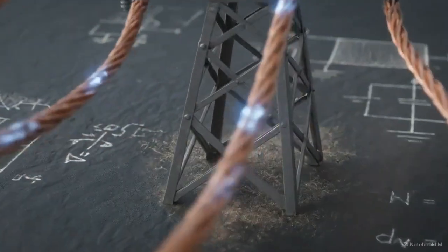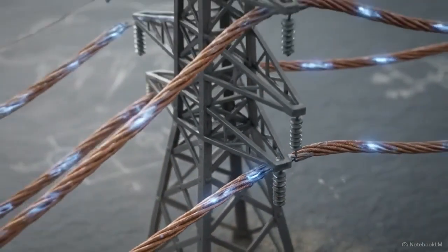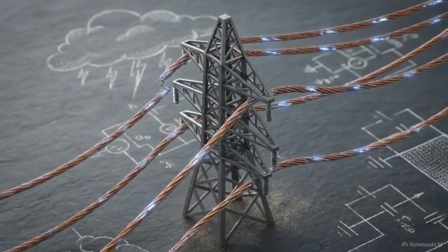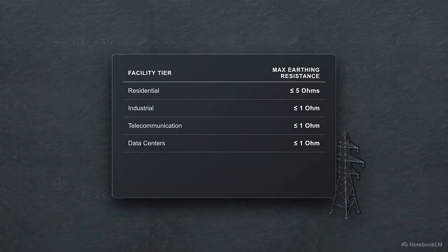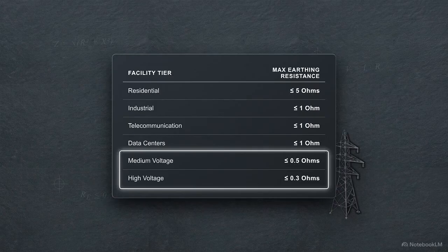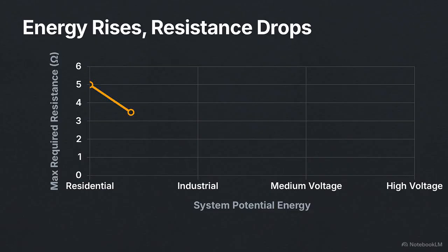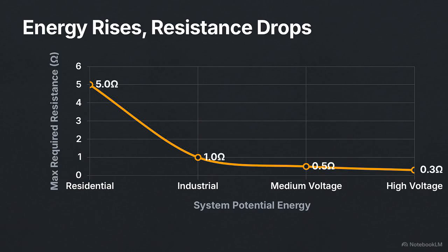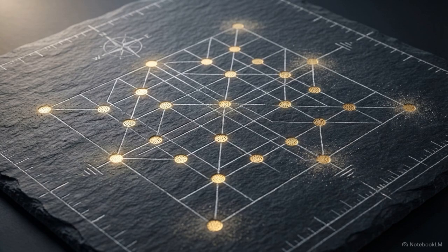Moving to the top tier of infrastructure, systems carrying massive electrical loads require the most frictionless path to ground mathematically possible. Utility-scale power transmission demands extreme tolerances. Medium voltage networks are restricted to 0.5 ohms, while high-voltage systems must achieve an earthing resistance of 0.3 ohms or less. We see a direct inverse relationship. As the potential energy of a system increases, the required resistance of its safety pathway must drop closer to absolute zero. An earthing system is an active, heavily engineered mechanism that requires exact physical measurement.